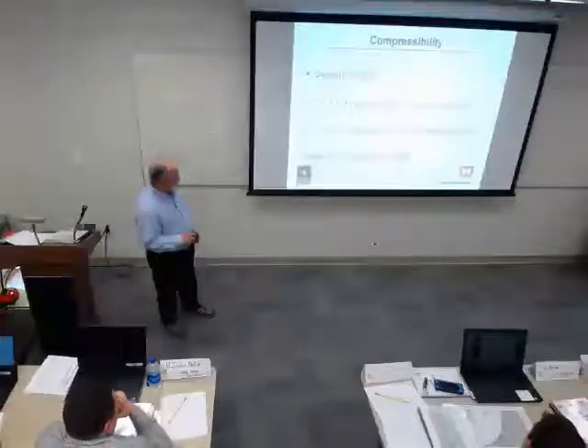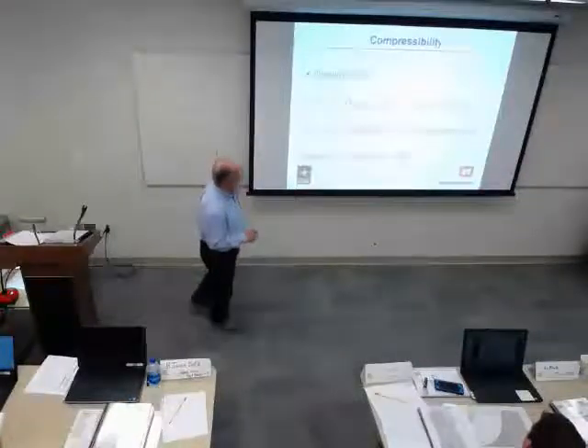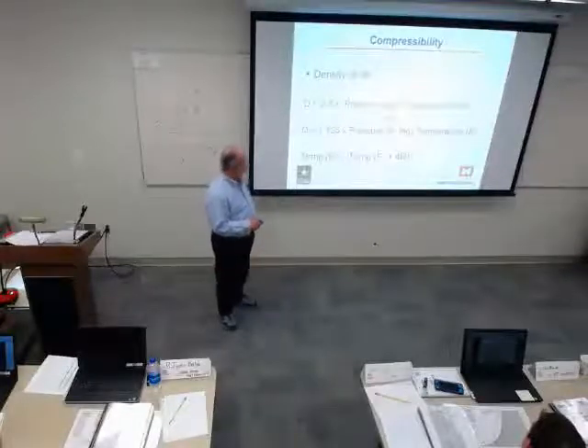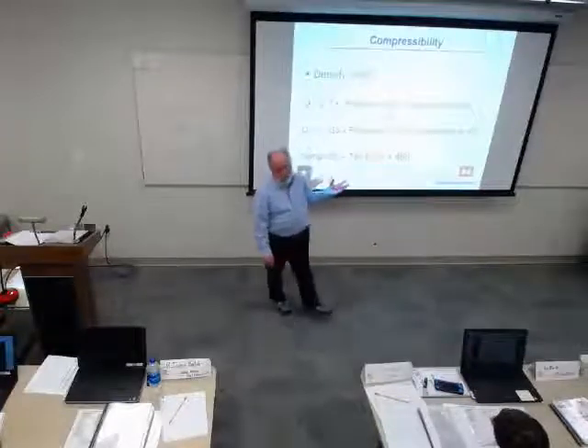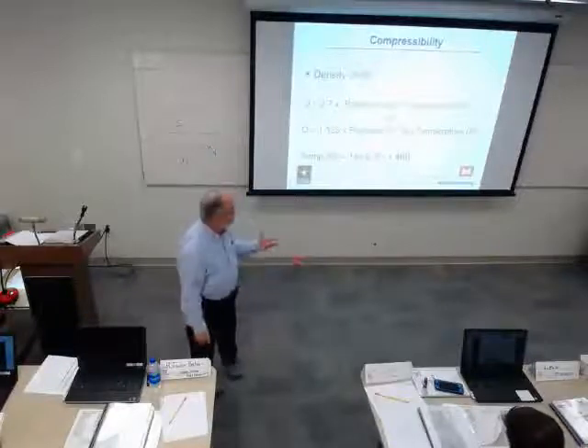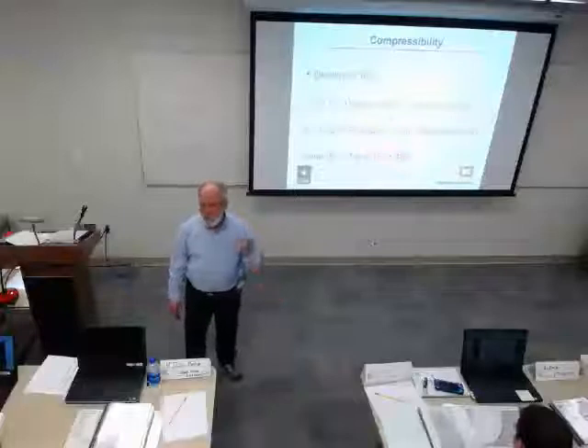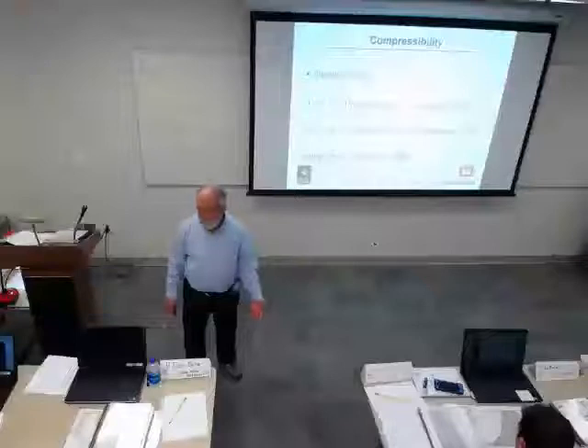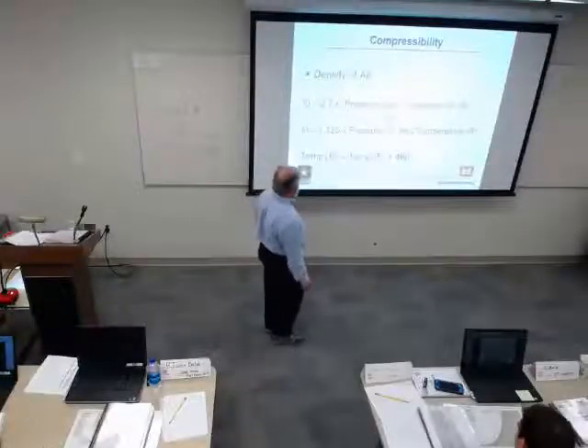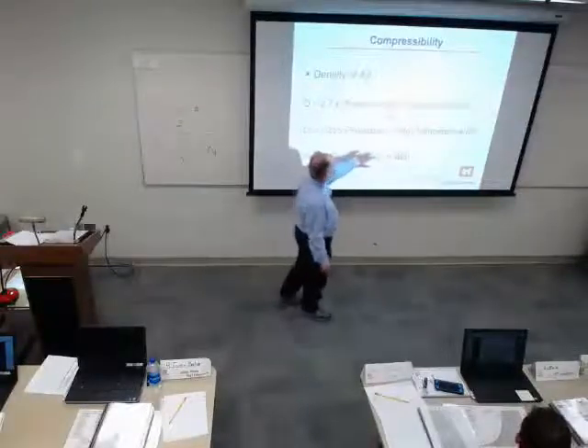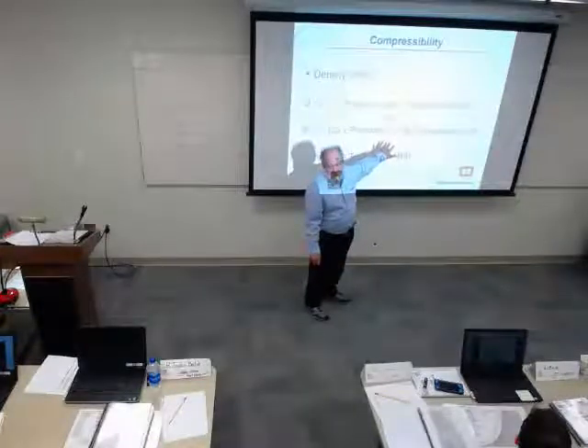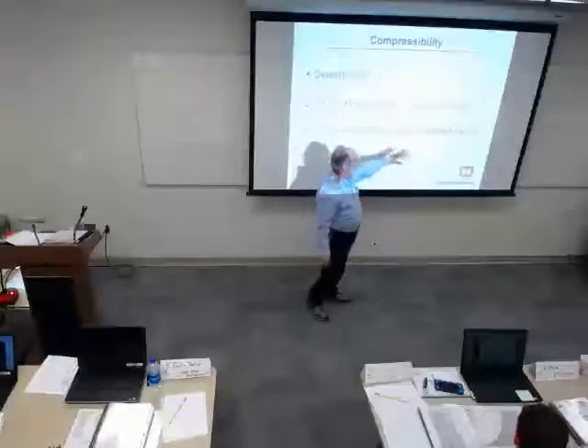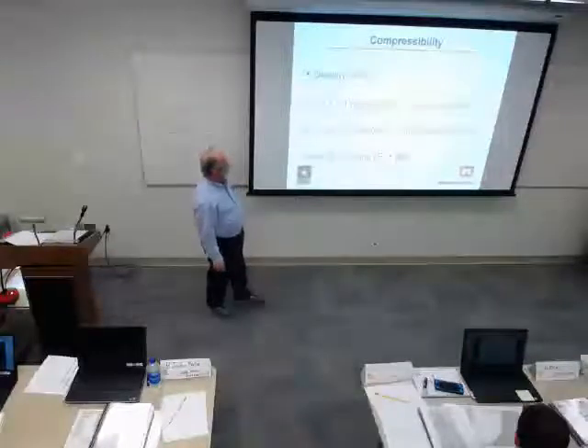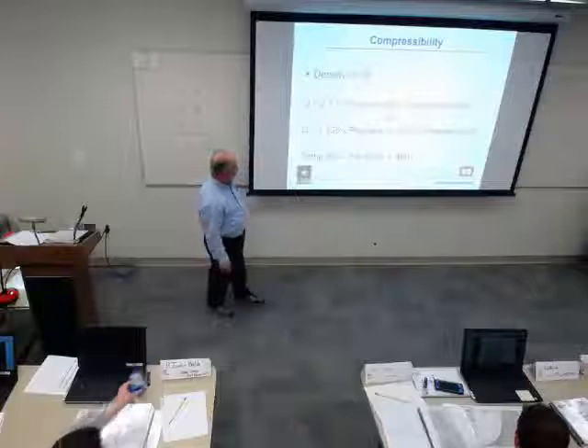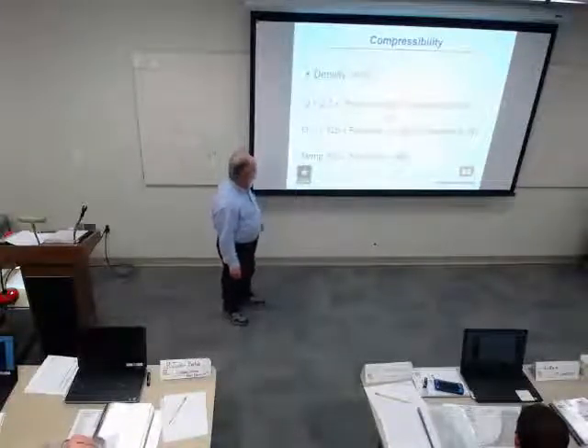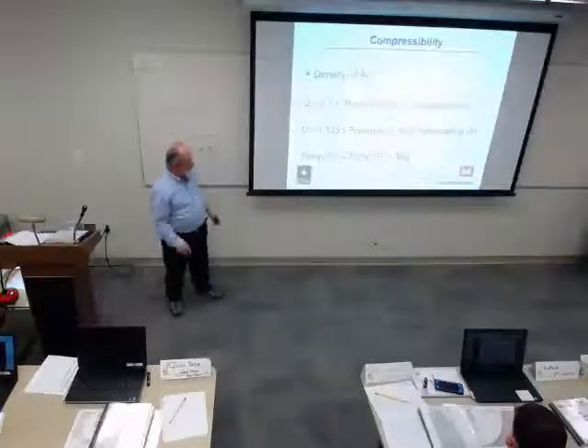Let's see here. Density is equal to 2.7 times the pressure in psi divided by the temperature in degrees Rankine. That's that R. When you're at 0 degrees Fahrenheit, you're at 460 degrees Rankine, because the idea of Rankine is absolute zero, which is 460 degrees in Fahrenheit increments below 0 Fahrenheit. So that's the R. Density is also equal to 1.325 times the pressure in inches of mercury, which we don't use a lot, but the weather guys use that a lot. The barometric pressure is in inches of mercury, divided by the temperature in degrees Rankine. So for density with pressure in psi, you multiply by 2.7. With pressure in inches of mercury, you multiply by 1.325.